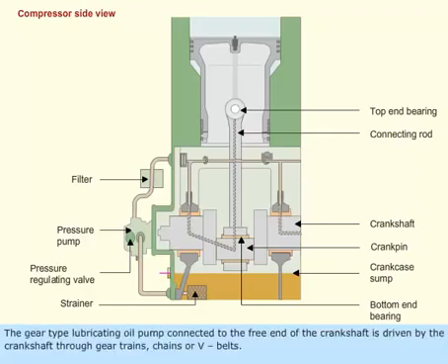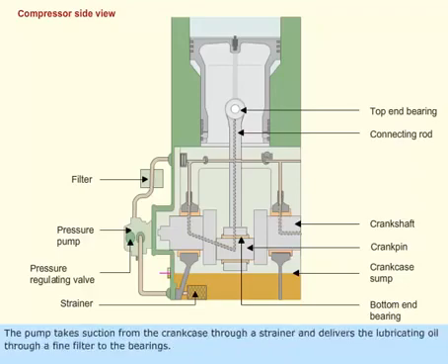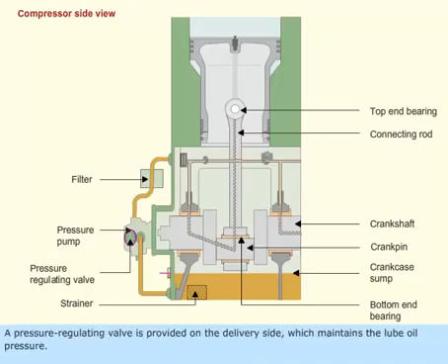The gear type lubricating oil pump connected to the free end of the crankshaft is driven by the crankshaft through gear trains, chains, or V belts. The pump takes suction from the crank case through a strainer and delivers the lubricating oil through a fine filter to the bearings. A pressure regulating valve is provided on the delivery side which maintains the lube oil pressure.